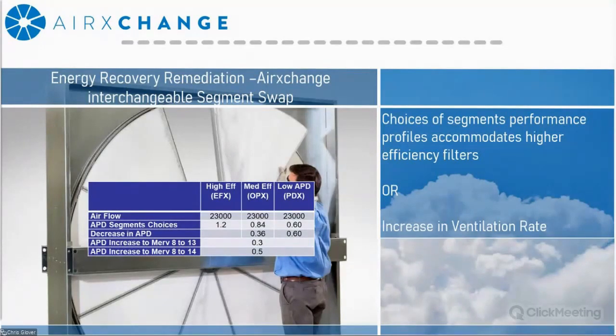One thing you may consider when approaching this is what we consider a segment swap, where you can achieve either higher airflow, higher filtration, or maybe even a combination of both. The Airxchange segments are interchangeable based upon diameter, and we offer three different varieties of segments. We have a high efficiency segment, we have a medium efficiency segment, and we have a low pressure drop segment. As you move from the high efficiency segment down to the lower efficiency segment, it allows you to either move more air across the heat exchanger surface or lower the pressure drop to compensate for some higher filtration.